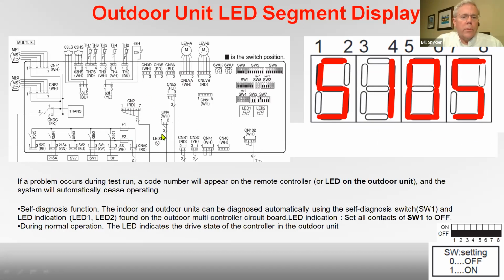we don't have those on here. They're not showing on here, but if this was addressed as 51, it's telling you that that 5108 is coming from this outdoor unit. It might say 5108-22, and that might be an indoor unit. So it kind of gives us an indication of where the fault is coming from.